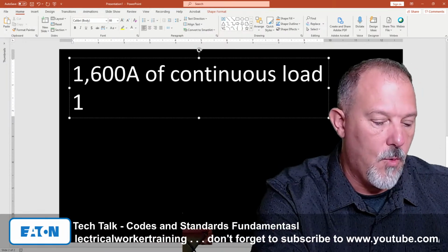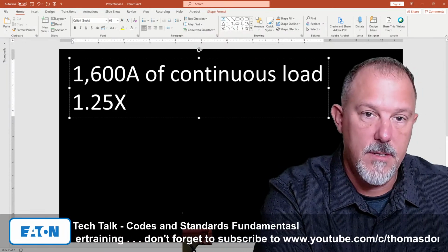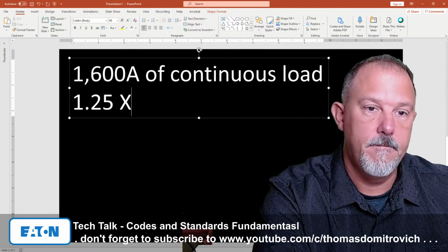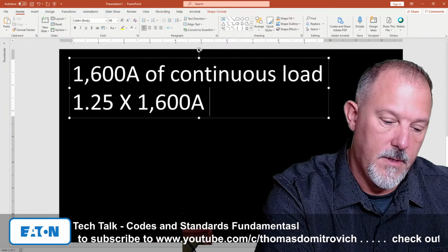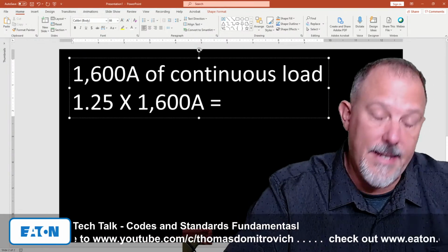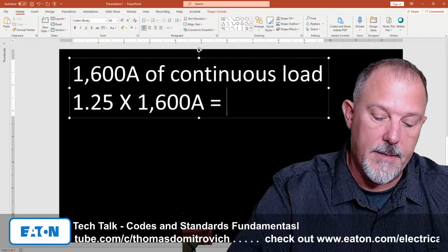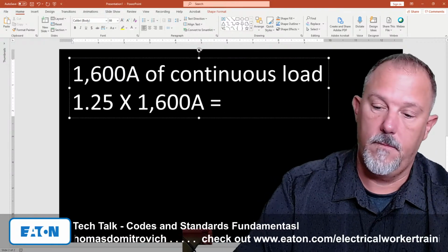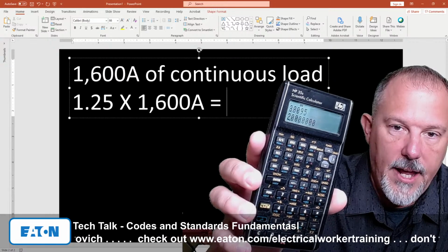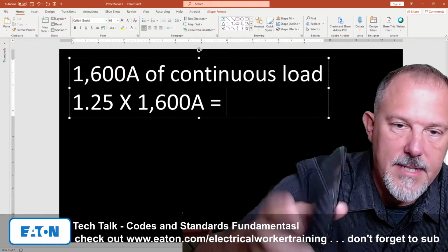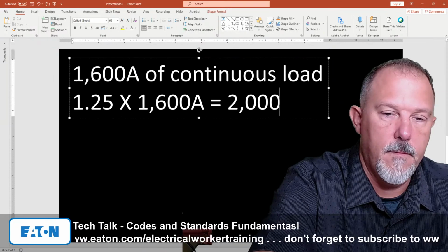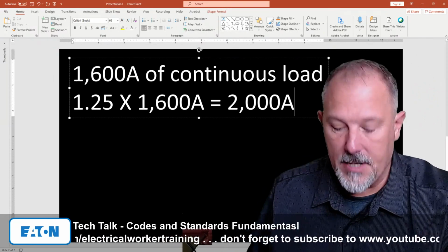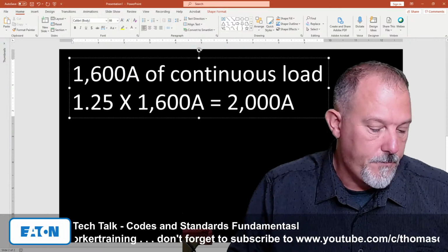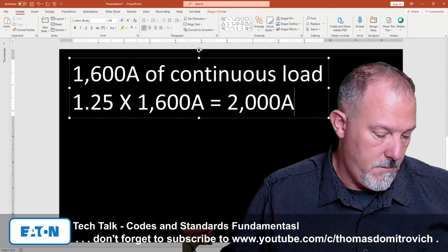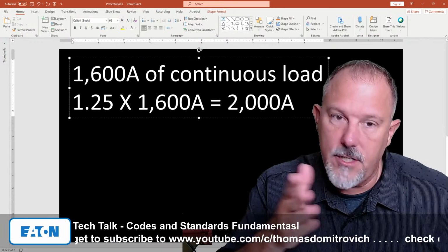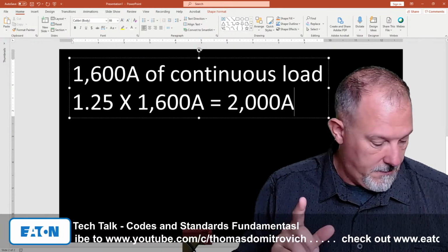We take 1.25 times 1,600 amps. And what do we get? We just did it, but I'm going to do it again. 1.25 times 1,600 is 2,000 amps. Now, if I had this in an application, because let's say it's a branch circuit, I would go to 210.19 and 210.20. Those are the two key sections.